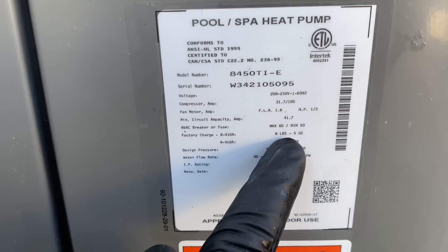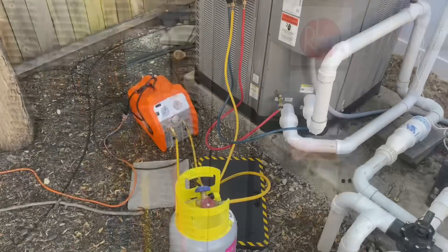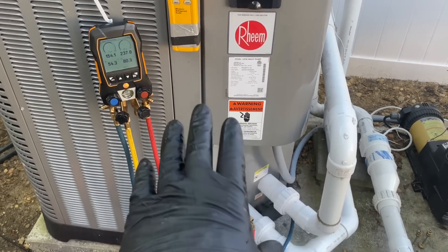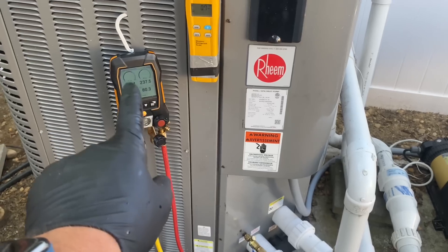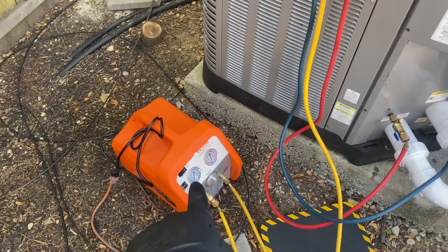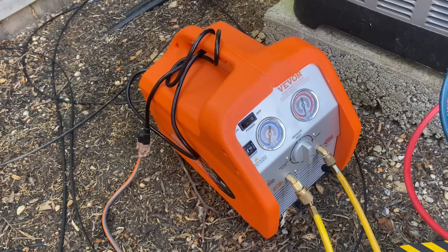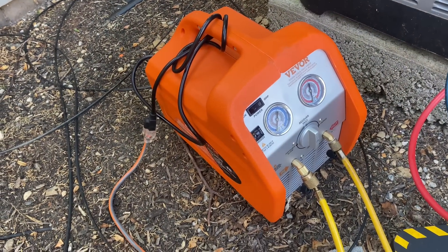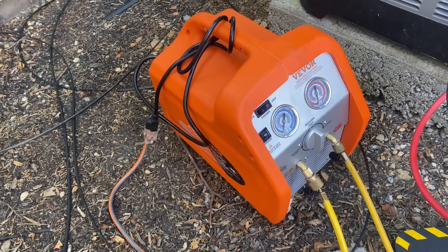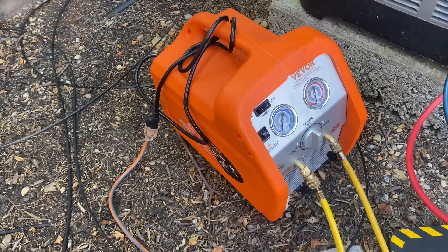All right, we have eight pounds, five ounces of R-410A in here. Let's start recovering. Nothing really changed on the test port side with the manifold. I got my yellow charging hose hooked up to the VEVOR — this is my recovery machine. VEVOR was nice enough to send that to me for testing and evaluation, to document my use of it on my social media channel. Big shout out to VEVOR.